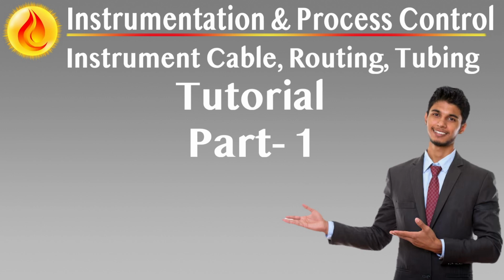Cabling for digital and video signal transmission. Instrumentation systems incorporating microprocessor-based control, digital communications, or video surveillance require cabling optimized for data integrity, bandwidth, and noise immunity. Digital signal cabling may use screened twisted pairs, coaxial cables, or fiber optic lines depending on application demands. For short to medium distance communication within protected areas, screened twisted pair or coaxial cables may suffice, provided shielding is effective and terminations are properly grounded.